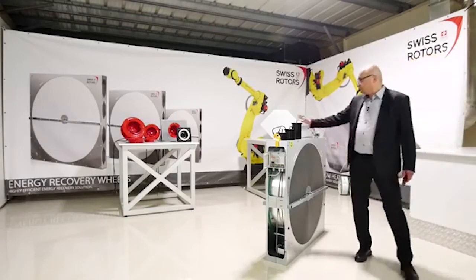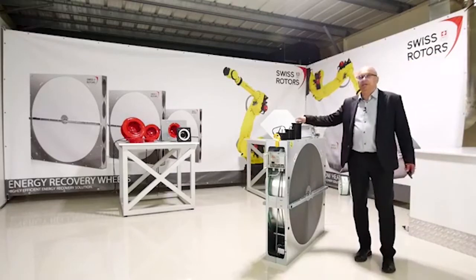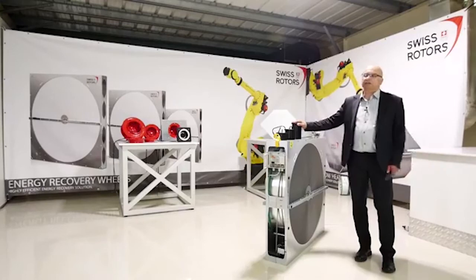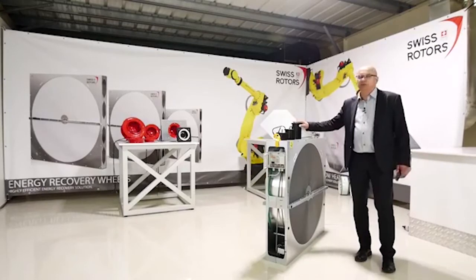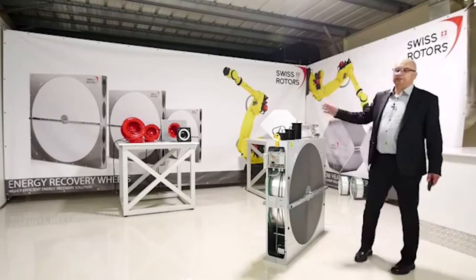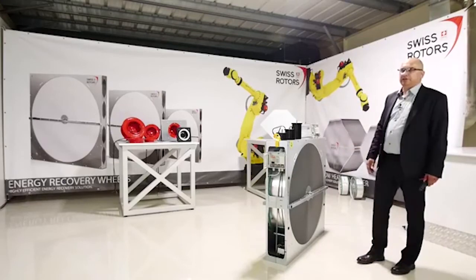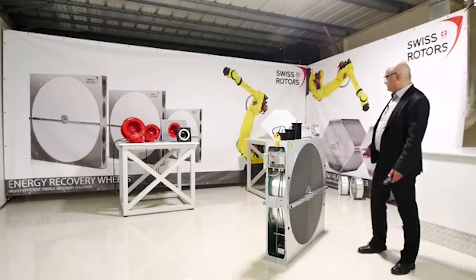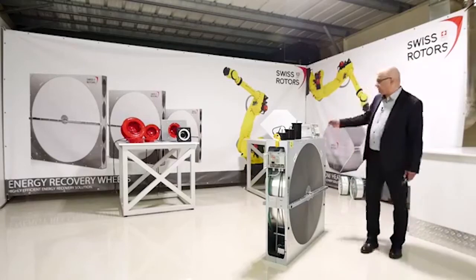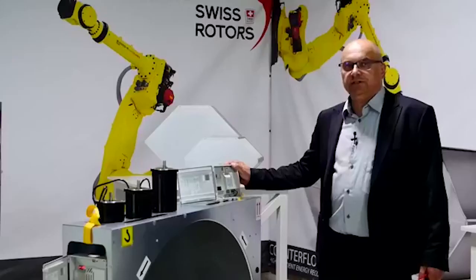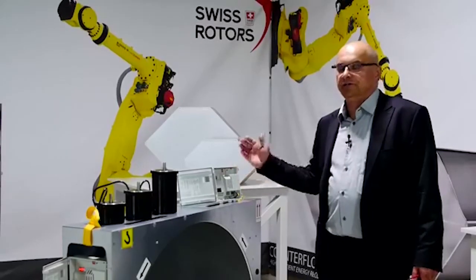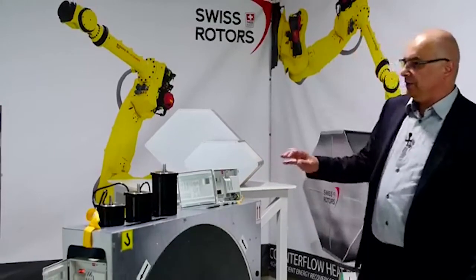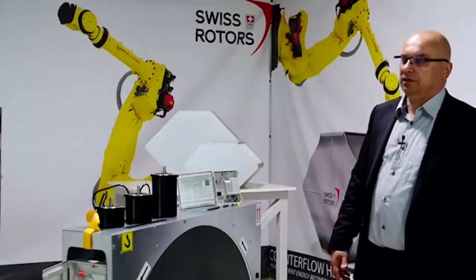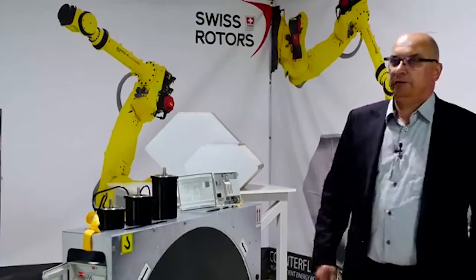And the motors are 3-phase. So sometimes in the specification, if somebody asks for a 3-phase drive, you can say yes, I have a 3-phase drive, because the motors are 3-phase. In some cases when they need a single-phase drive, you can say yes, this is a single-phase drive, because the controller's input is single-phase and output is 3-phase. So you can comply with all the requirements from the project.